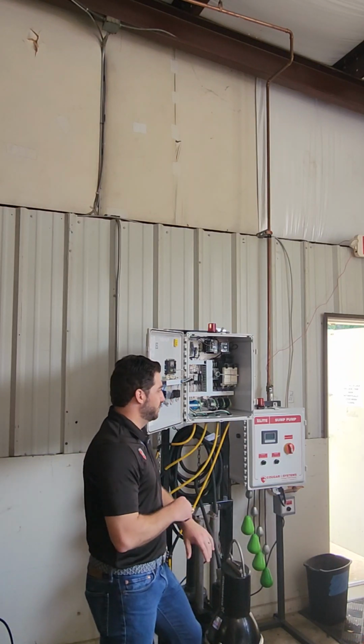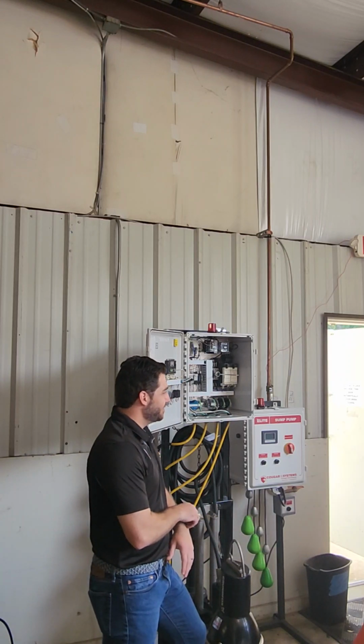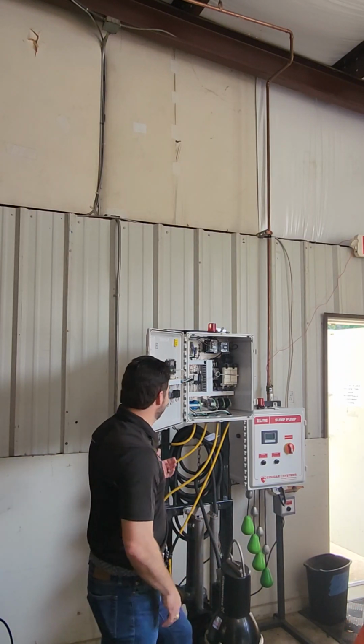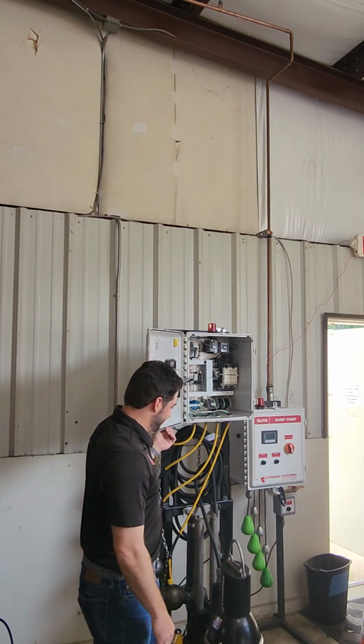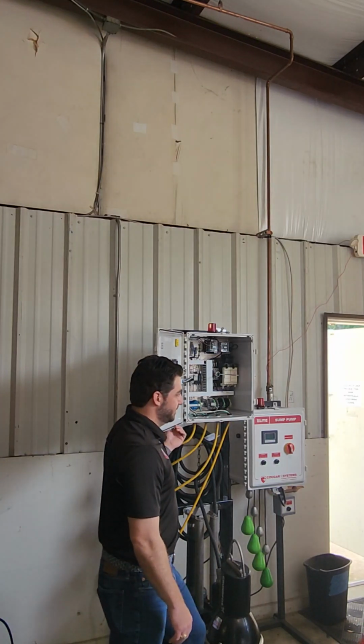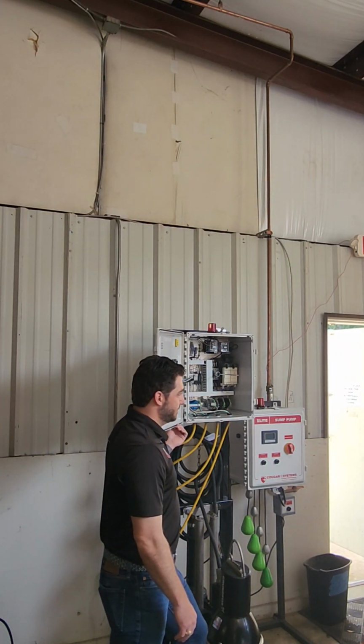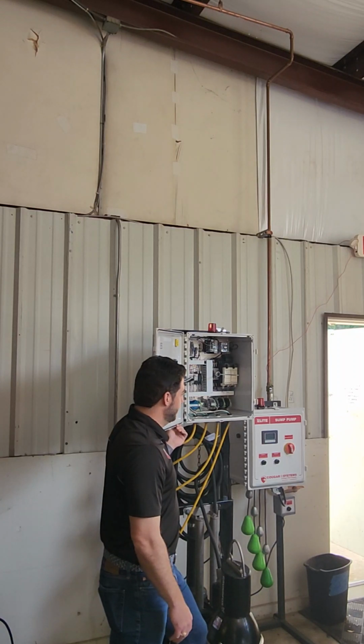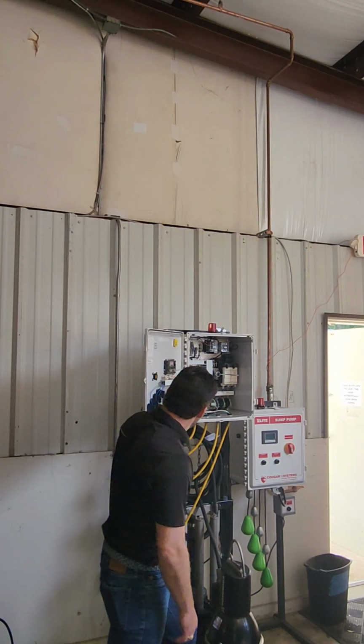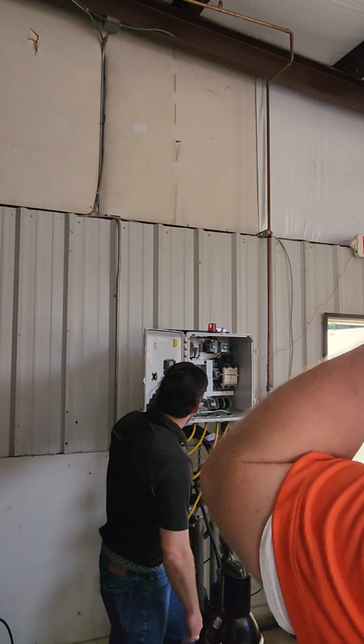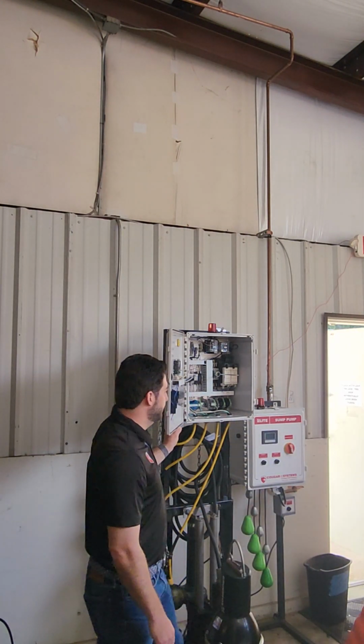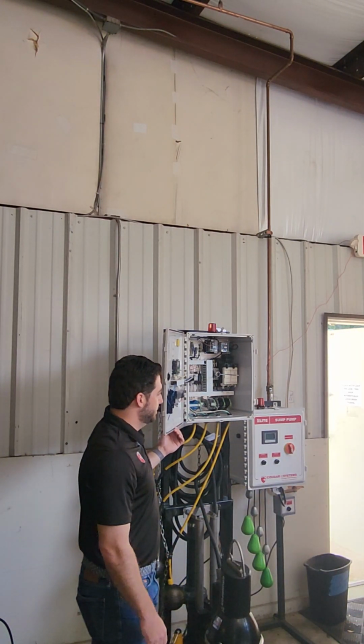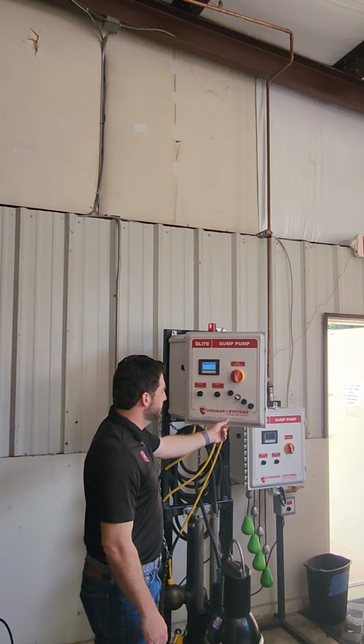So, I don't know if you want to add anything on that. That's a dumb alarm for me. I think of it, moisture will activate it. If it's sitting in this humidity or whatever, it collects moisture and they'll set the alarm. Those customers turn it off, run it for a couple of minutes, it evaporates and dries off. But sometimes it stays active. But the pump can run the rest of its five, six years with the alarm.